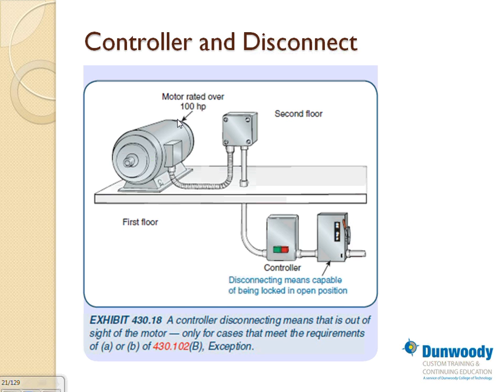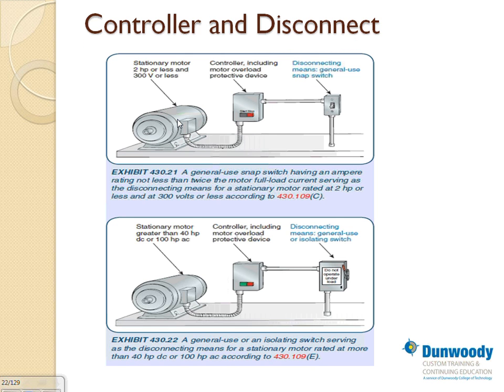So disconnect means capable of being locked in the open position. So again, if that's the situation, you have to adhere to the exceptions. The rule is you have to have a disconnect within sight of the driven machine, the motor that drives the machine, and the controller. Exceptions: in industrialized locations where maintenance is done by qualified people, you can have it in another location where you can lock it.